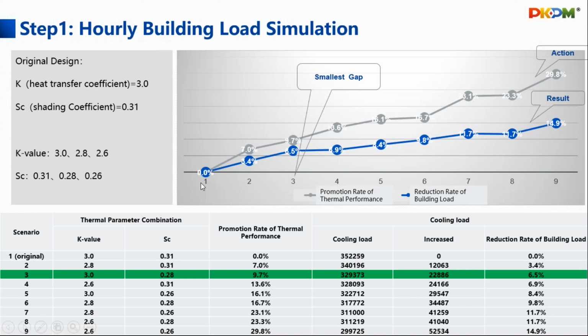The first step is to choose the suitable glass for the curtain wall. We wanted the glass to have good insulation performance, but we didn't want it to cost too much. So we decided to use 2 factors. One is the K value, quite similar to the U value, which is the heat transfer coefficient. The other is the shading coefficient, representing the ability of glass to resist sunlight. Usually the smaller the shading coefficient is, the better the thermal performance of the curtain wall. So for each factor we prepared 3 numbers and combined them into 9 scenarios.